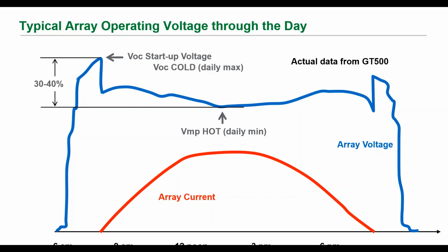So when you design a 1000-volt DC PV system, you need to connect more panels in series and parallel combination to reach the required watts. There is a required power and a required voltage. Okay, so early in the morning, you see that your panel will see high voltage because current will be less, and it's a function of temperature. Voltage has a negative temperature coefficient. So if your temperature is less, voltage will be more. If the temperature increases, voltage also will decline. So that's all.